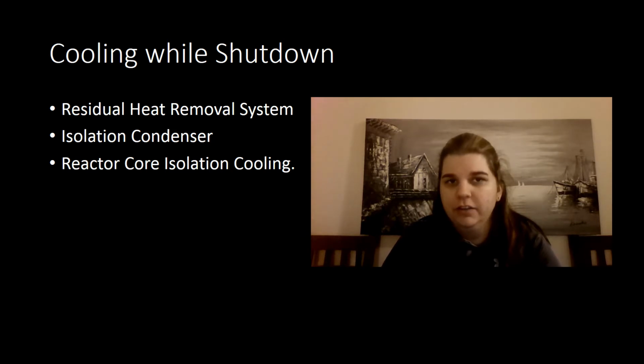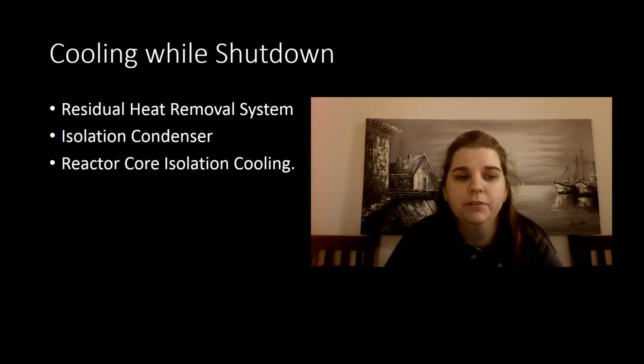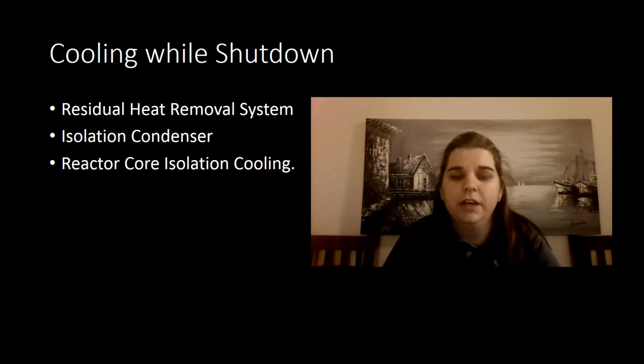The next is the isolation condenser. Unit 1 of Fukushima has an isolation condenser which is operated by DC power. The isolation condenser system directs reactor steam to an external condenser in order to cool the reactor core. Finally, there is a reactor core isolation cooling system. Units 2 through 5 in the Fukushima plant have this system. The reactor core isolation cooling system is put into operation automatically, but is powered by the DC battery system. The system provides makeup water to the reactor pressure vessel from either the condensate storage tank or the suppression pool to ensure that the reactor core is covered by coolant and the heat is removed.